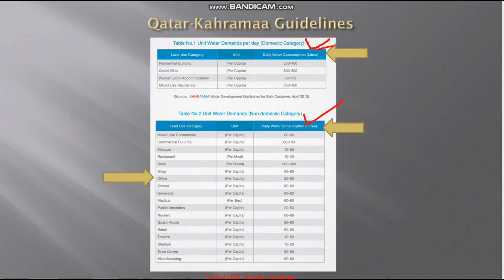In the Qatar Kahramaa domestic category we have residential buildings, Qatar villas, labor accommodation, and mixed-use residential. In the non-domestic category come commercial buildings, offices, schools, universities, and all others. For the Saudi Building Code, SBC 701 covers plumbing and SBC 702 covers drainage. There are no specific daily water consumption requirements in the Saudi Building Code — it generally follows the International Plumbing Code. Whenever executing a Saudi project, the daily water consumption value is taken from the project specification.